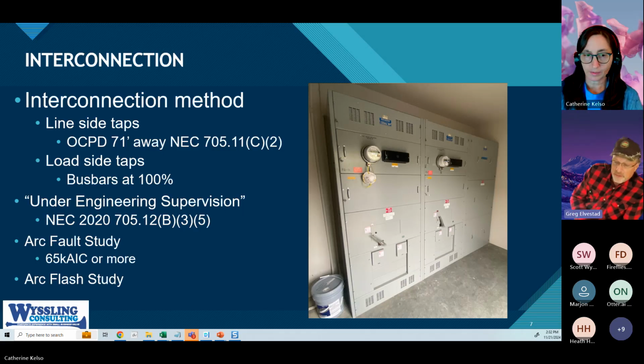A couple of things on that. Arc fault studies, like I said, are part of the under engineering supervision. Commercial projects and services larger than 200 amps in specific markets require an arc fault study all the time, to make sure that the interrupting capabilities of the equipment installed are equal to or greater than the available energy at the point of the assumed fault location.